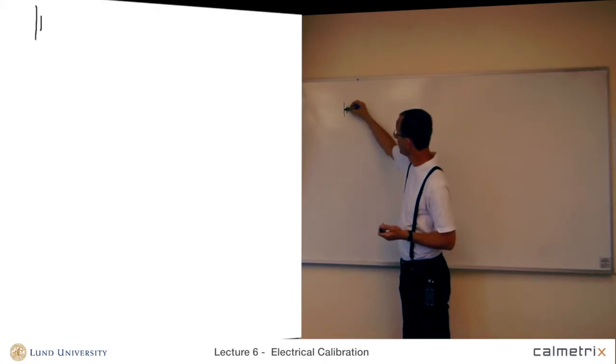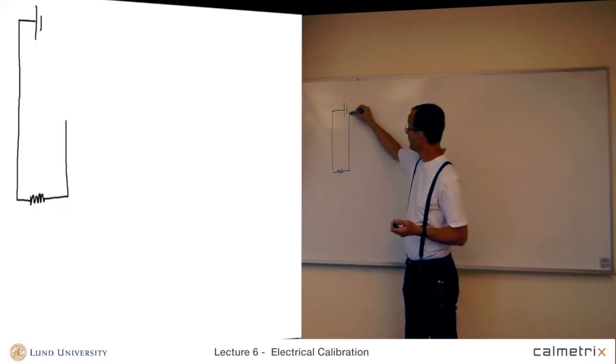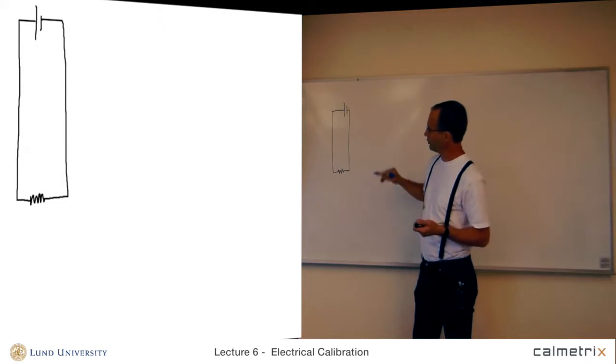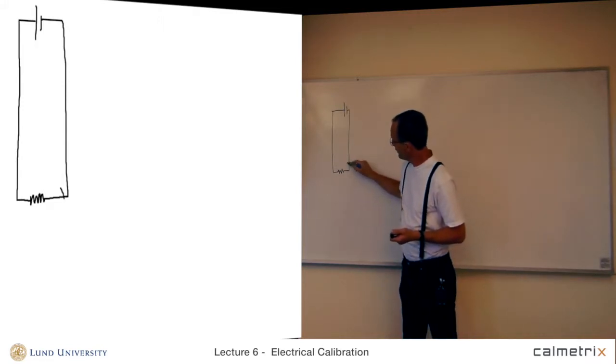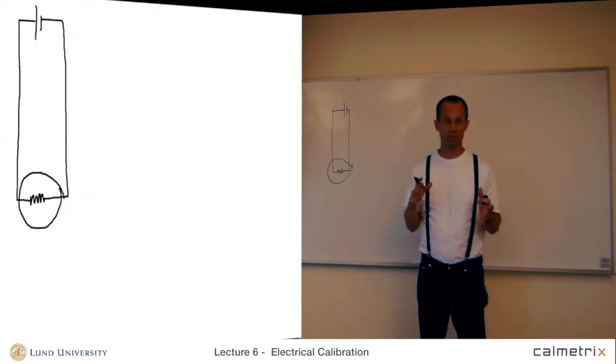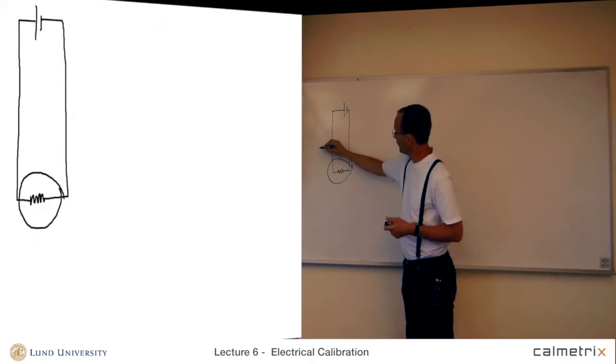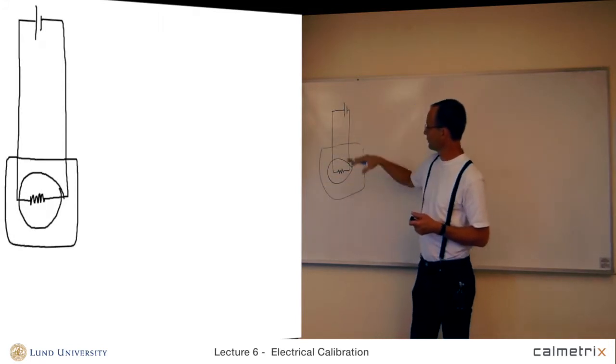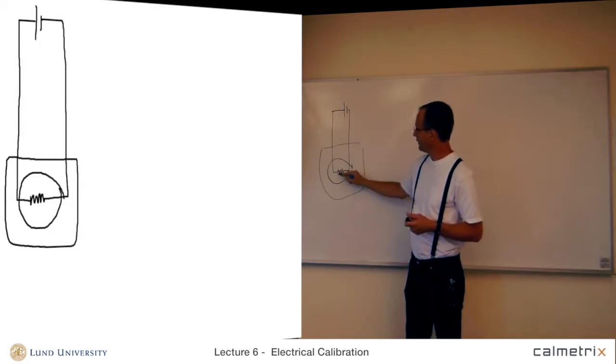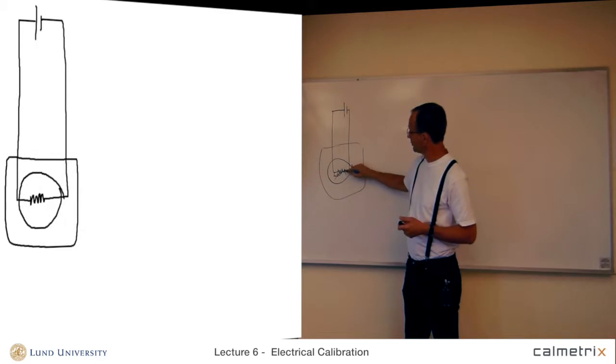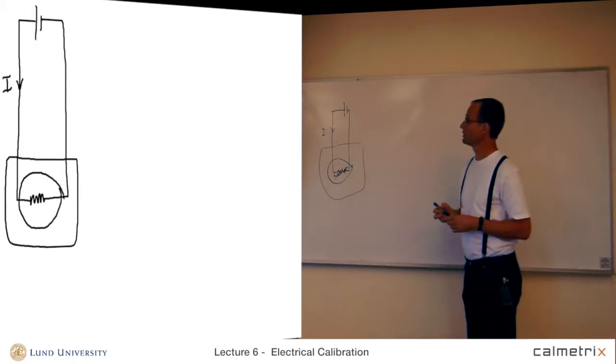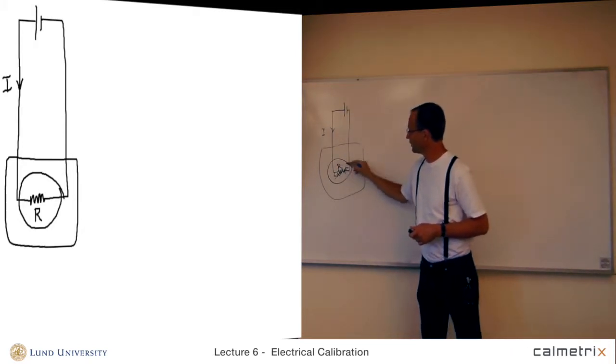We have a voltage source, the battery or a voltage source outside the calorimeter. Then we have leads going into the calorimeter and inside the calorimeter we have a heater and going back to the voltage source again. So, this is inside the calorimeter on the sample side. This is the thermostated environment. There we have the voltage source outside and the heater close to the sample. The current, which is i here, is measured and we know the resistance of the heater.